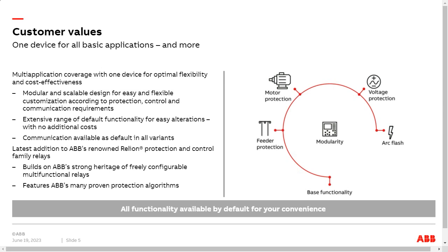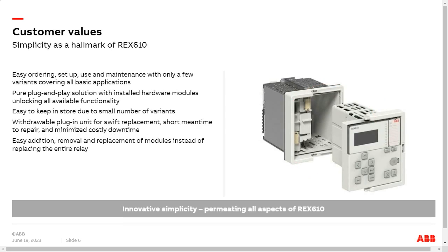And of course, as already mentioned, it's a Relion product and it has the proven algorithms from that family. So, easy to order, set up and maintain, with only a few variants. I will show this later, when I can show the order code, for example. And a plug-and-play solution with installed hardware modules unlocking all available functionality. If you take a look inside the case, you can see that in that module there are two connectors, so there are two modules installed. It's very easy to pull out a module, or add an additional module, so you get the desired functionality out of the device. This can be done already at the ordering stage at the factory, or you can order a module later on and update the device to support the new functionality.